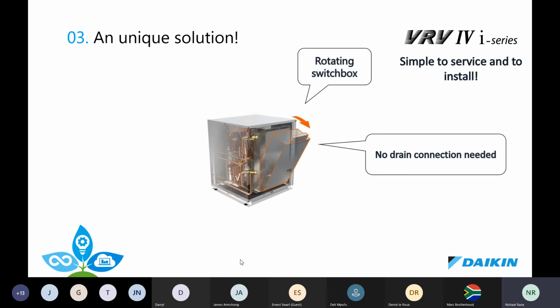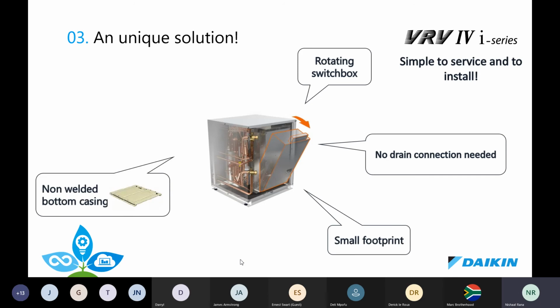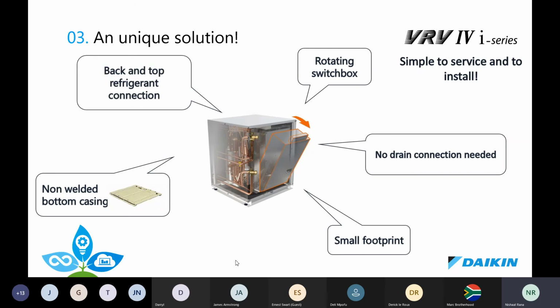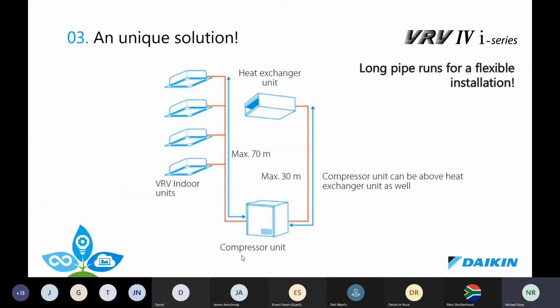Easy access, simple to install, no drain needed, small footprint, non-welded bottom casing, so you're not going to get corrosion. Back and top refrigerant connection, so you could come in at the back of the unit depending on your layout, or come in at the top, depending on whether you want to put this higher on a cantilever bracket or whatever the case may be. The pipe runs are quite decent. From the air module, you can go up to 30 meters to the compression module. And from the compression module, being a 22 kilowatt system, you can go another 70 meters maximum to your last indoor.